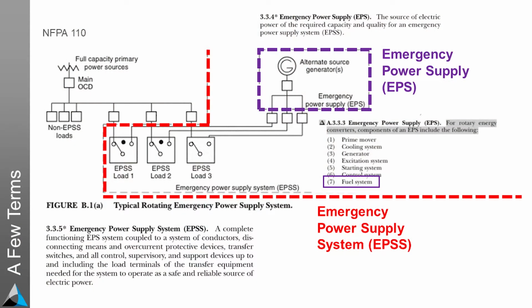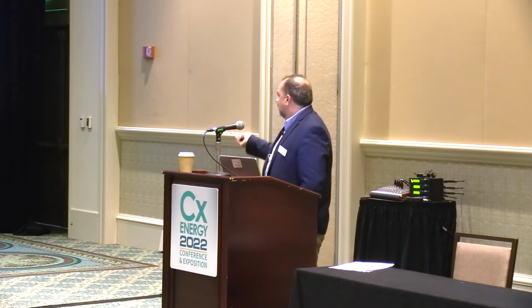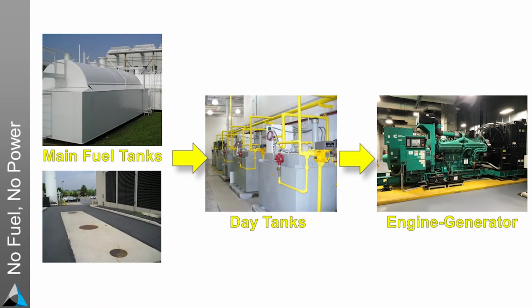And I'm backed up by that from NFPA 110. Just to go over some common definitions: I already said EPS, that's a term that means emergency power supply, which is the generator and its switchboard and switchgear. But the EPSS, the emergency power supply system, is the overall emergency system, which includes, if you could possibly read that purple part there, it says fuel system. So that's part of the system that we have to test, backed up by code.